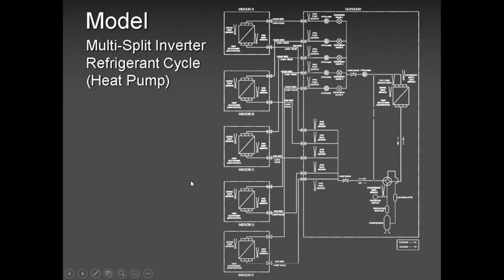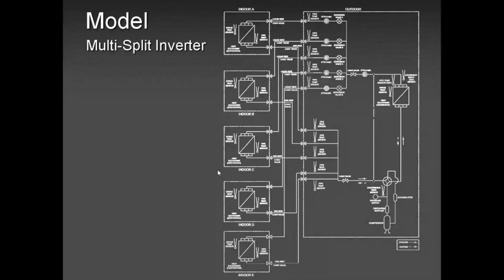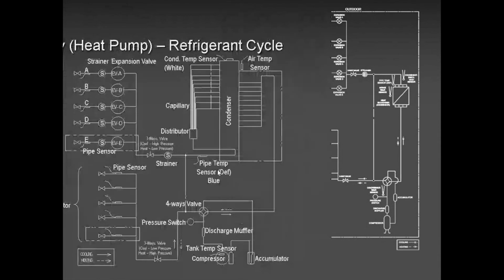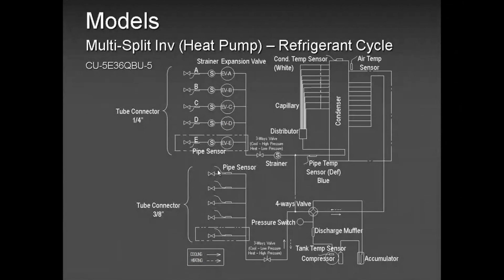Again, this slide is for training purposes. I would strongly advise you to read the installation manual based on the model you are installing. Don't tell me, oh, Paul said 49 feet, 24 feet, and that's about it. No. Please remember that you need to pay attention to the model that you're working on. It could be a different model. All models are not the same when it comes to pipe length and height.